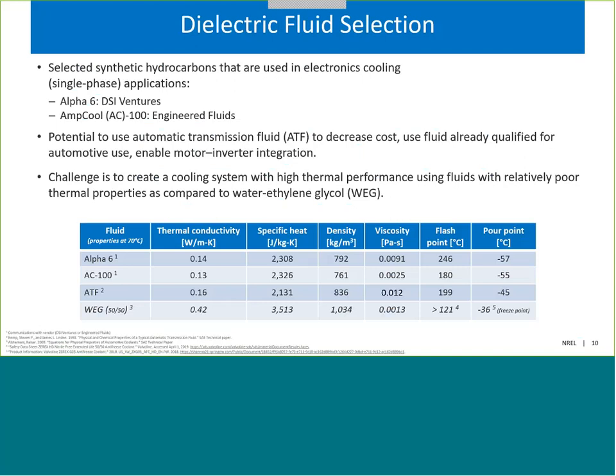There are various dielectric fluids that are available. In this case, we selected two synthetic hydrocarbons that are currently used in electronics cooling single-phase applications. One is Alpha-6, made by a company called DSI Ventures, and most of the modeling work that I'm going to be showing was done using this fluid. The reason we use this fluid is because it has a high flash point of 246, and that is ideal considering we're targeting a maximum junction temperature of up to 250 degrees C. The other fluid was AmpCool or AC100, made by a company called Engineered Fluids.